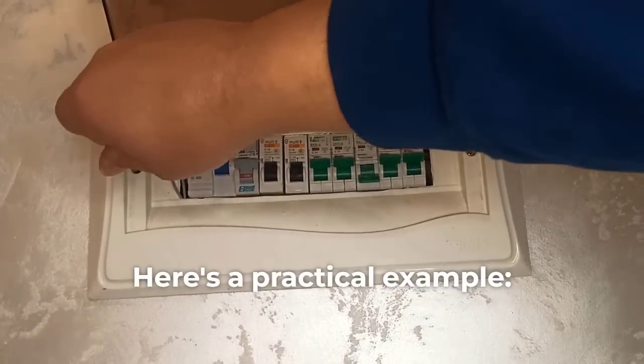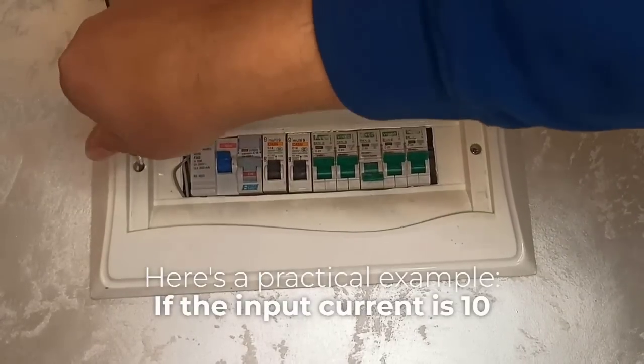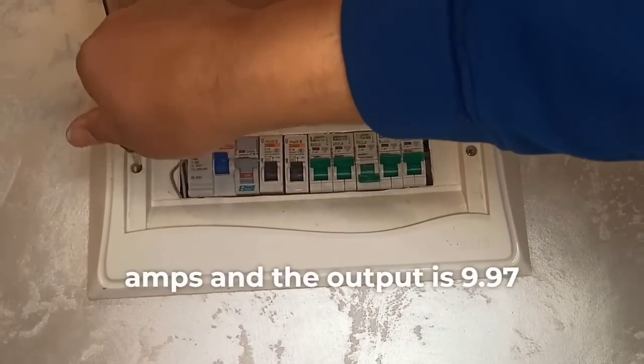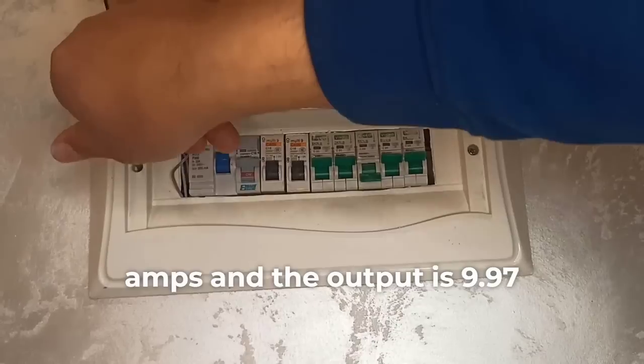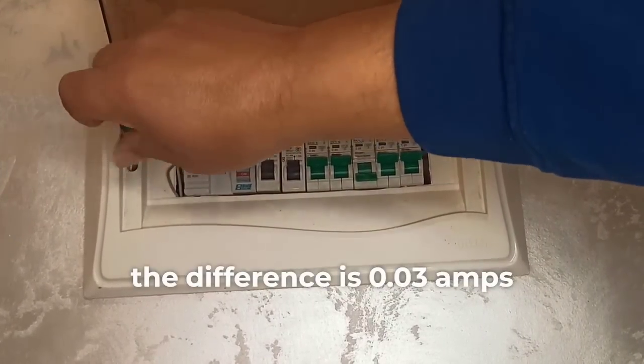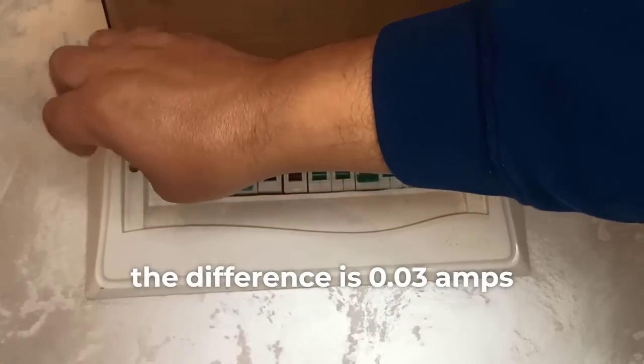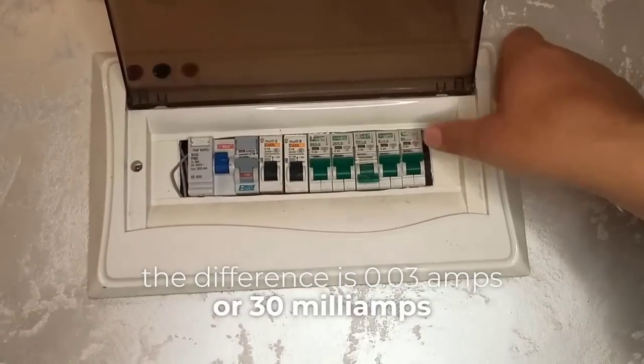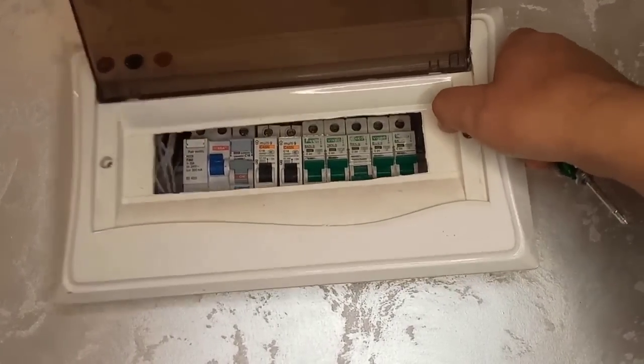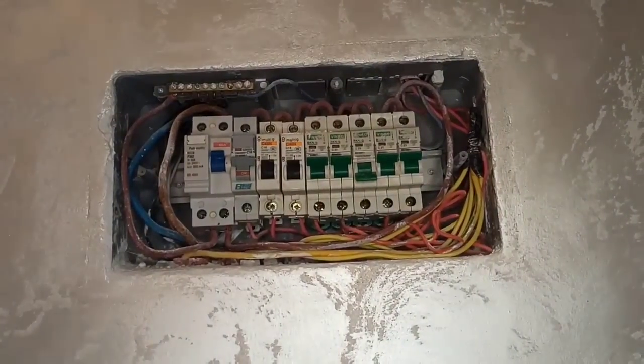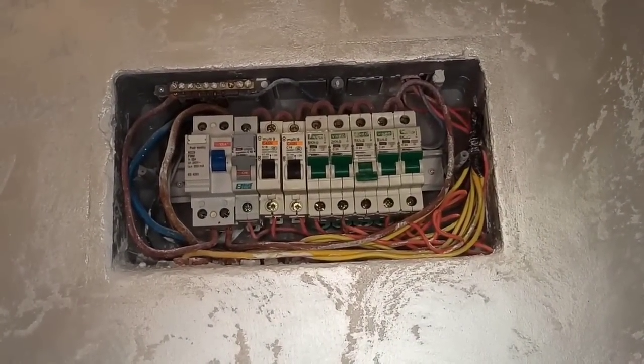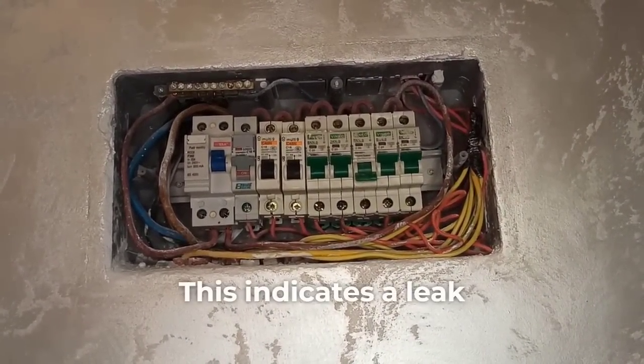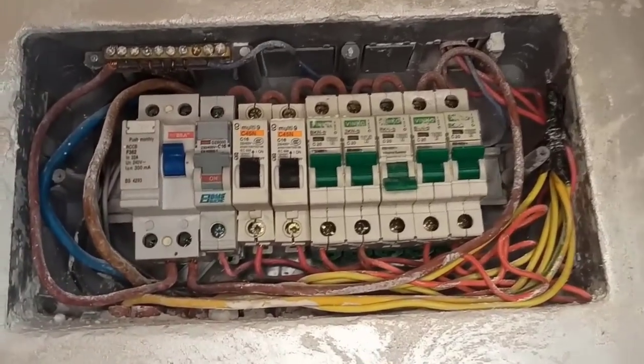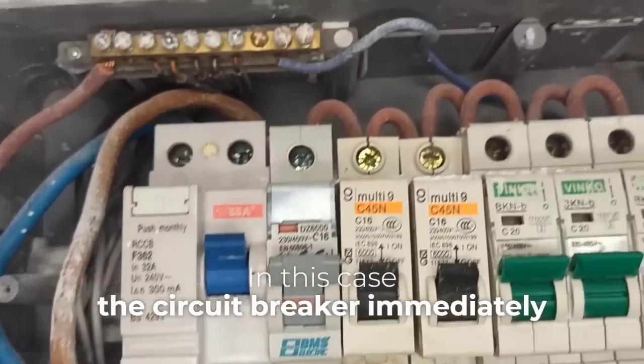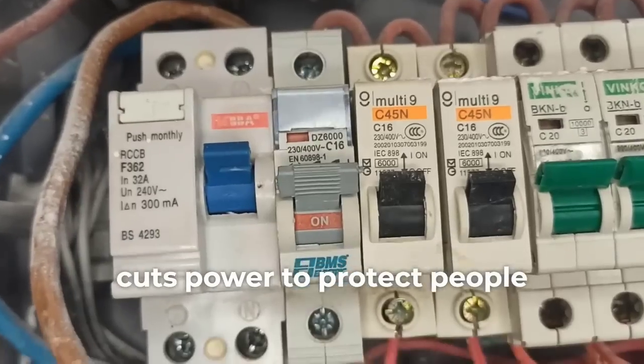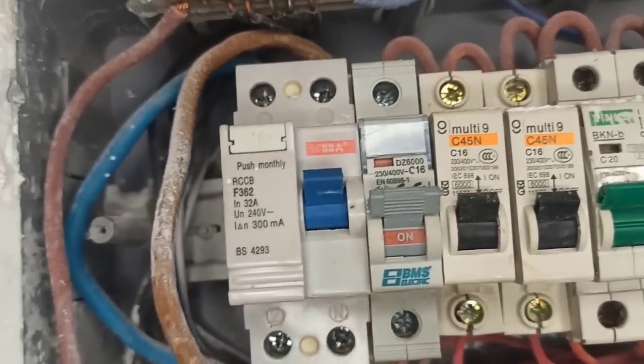Here's a practical example. If the input current is 10 amps and the output is 9.97 amps, the difference is 0.03 amps or 30 milliamps. This indicates a leak. In this case, the circuit breaker immediately cuts power to protect people and property.